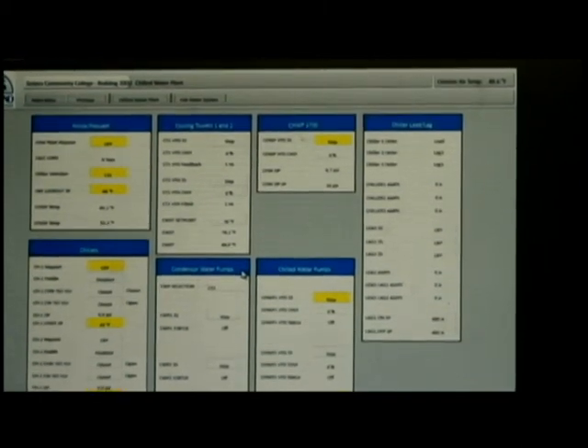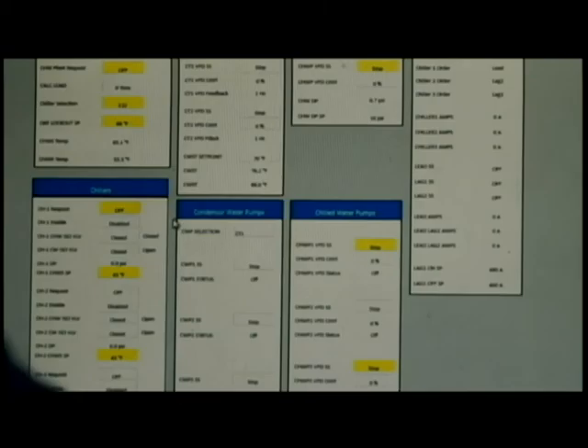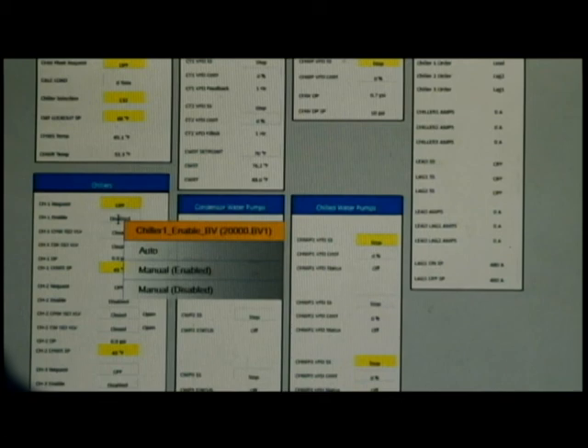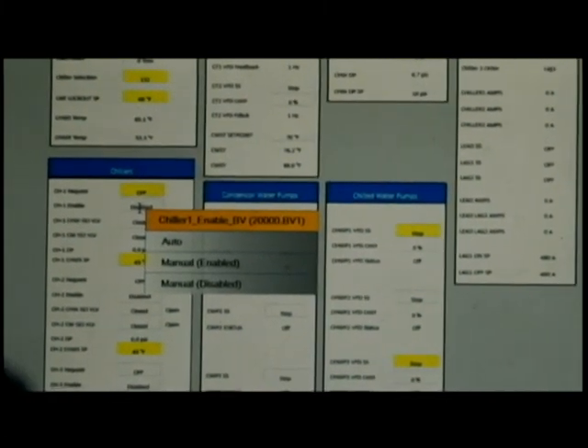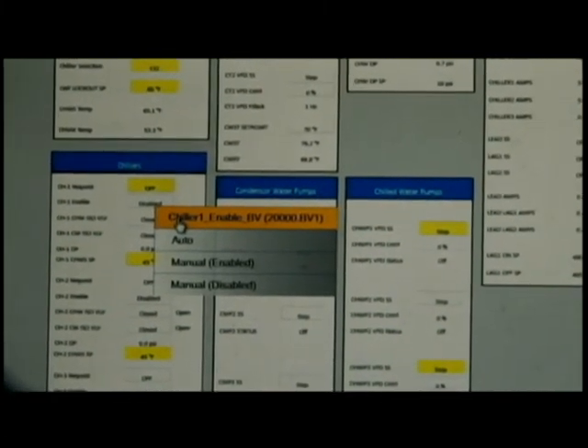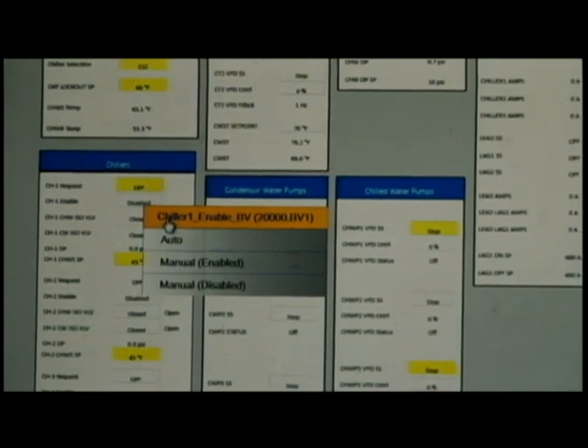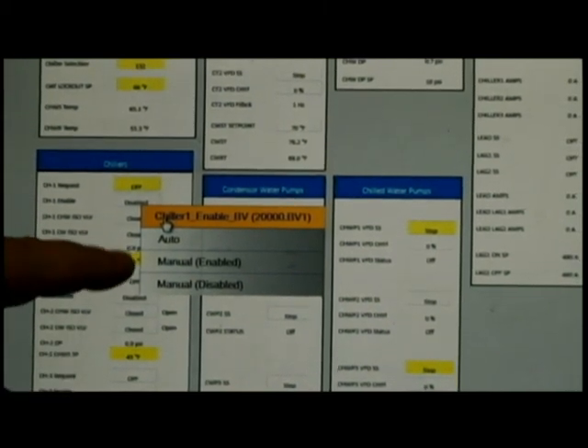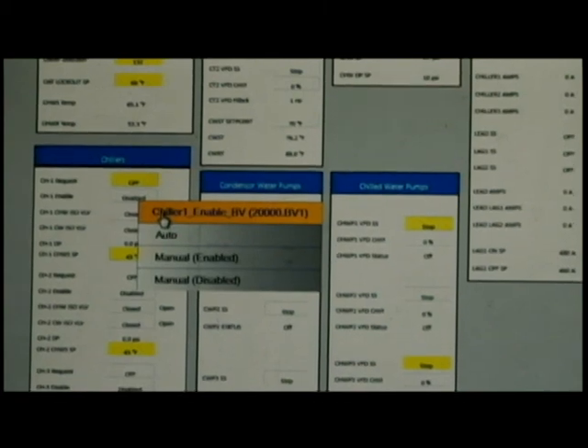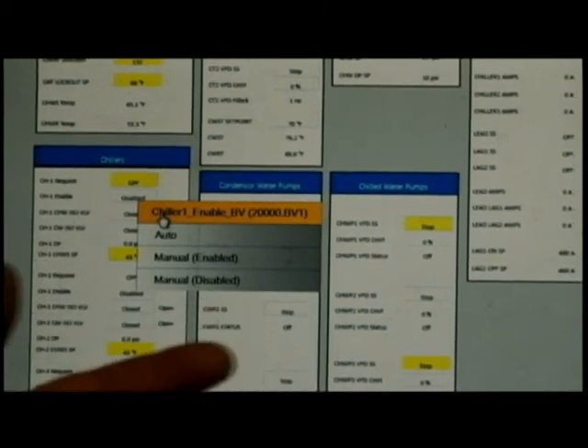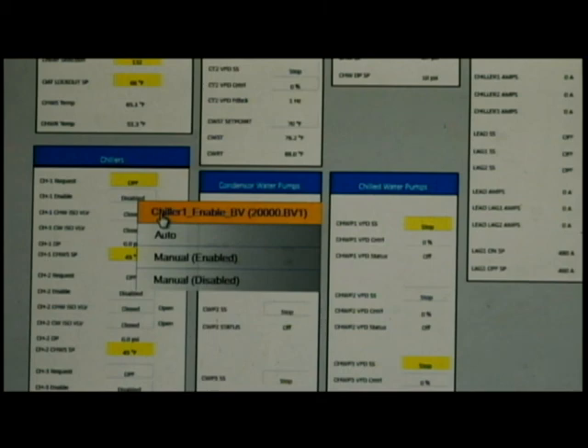One of the other things that's nice about looking at these points is if you need to find out what's going on, why isn't a chiller running, you can use that same mapping to come over here, hover over your chiller enable point. You know, it is a BV right now. On the binary variables and binary outputs, instead of a manual value option, you have a manual enable or disable, off and on, basically. Whereas the analog ones, you have to put a specific value in.